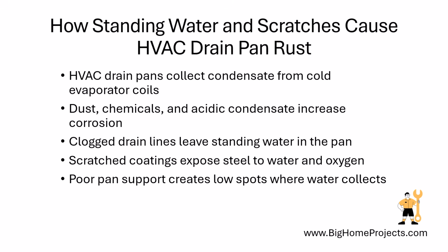Salt in the air can make this worse, especially near the coast or in areas where salty outdoor air enters the building. A less commonly noticed cause is an improperly supported pan that bends and creates a low spot where water collects. Check the pan during routine maintenance. Keep the drain line clear, and replace the pan if you see deep rust, holes, or water stains below it.